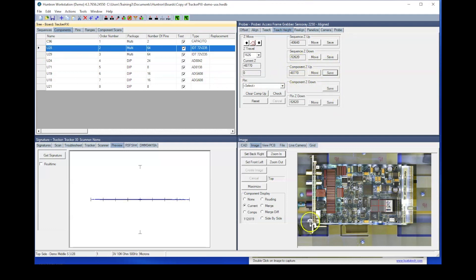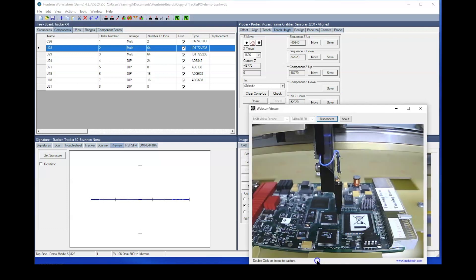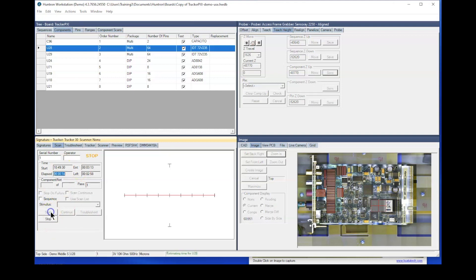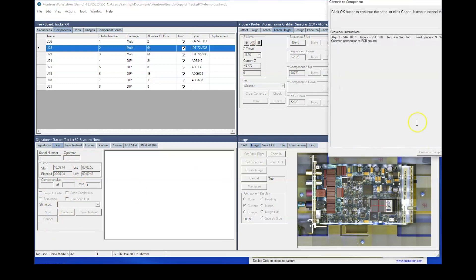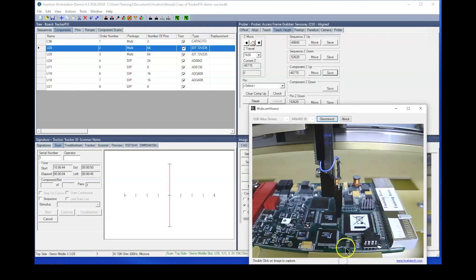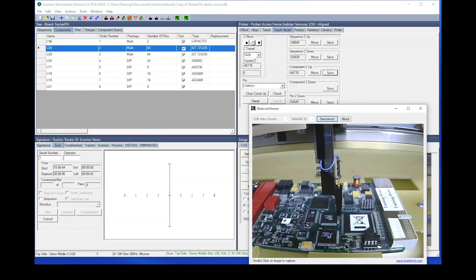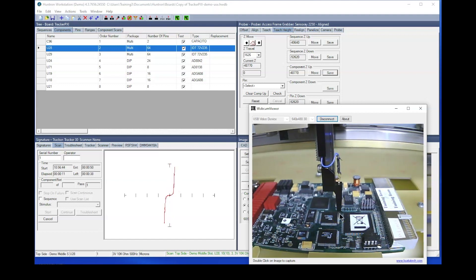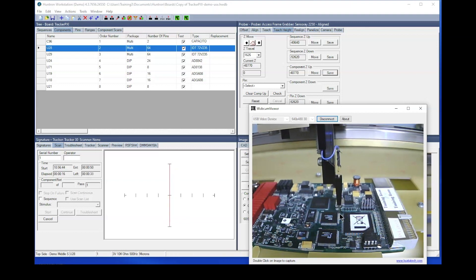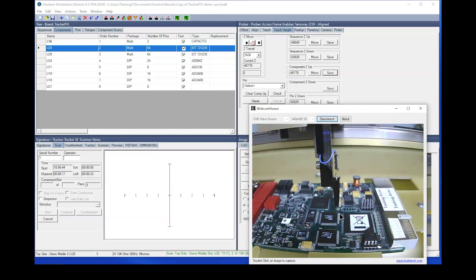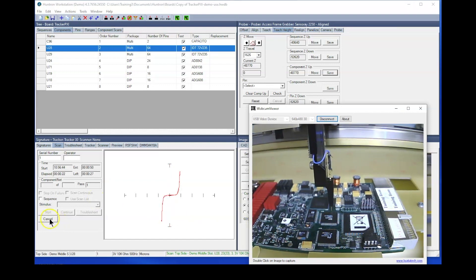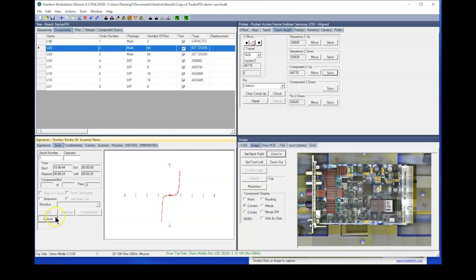So now let's watch this component probe. Go ahead and scan this guy. Just the individual component. Start and click OK. And I'll turn the video on here. So you can watch this probe down. See, it's going at a much lower level now. So the Z axis is no longer having to travel quite so far as it moves between pins. And you watch it go all the way down this row. And it goes over the corner right there. You see it probing the back side. That can help reduce your test times quite significantly, especially if you have a lot of components with a lot of pins.